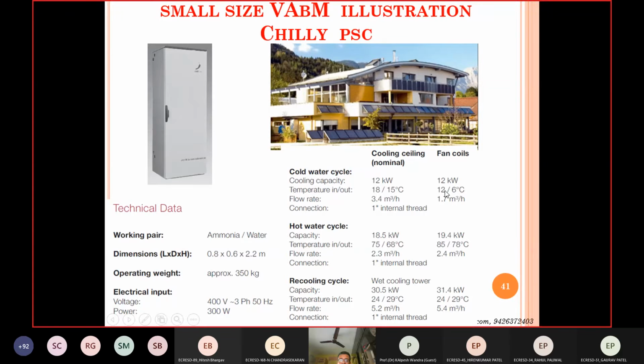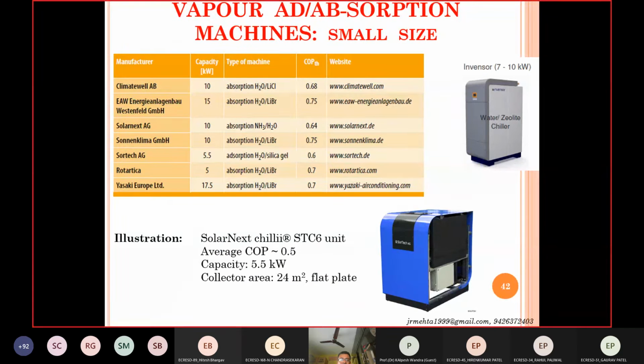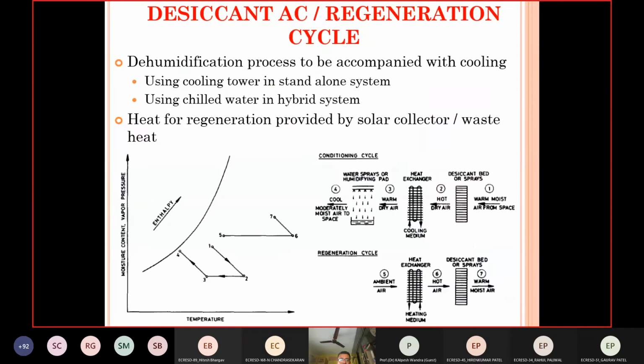Now when this is lower, what you find is that for your hot water cycle, the hot water that you need to supply, for this application you need a higher temperature of hot water, okay? While here the temperature range is lower. Okay. So when you want cooling at a lower temperature, you also need to provide the heat at higher temperatures. Otherwise, your COP will go down. Right?